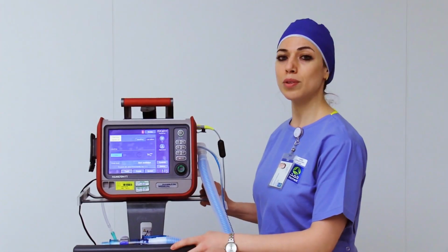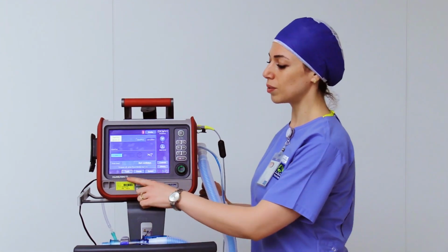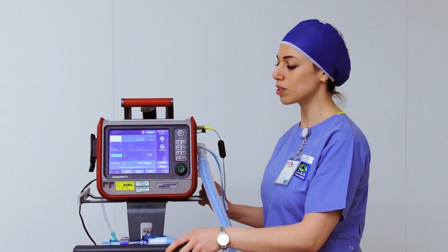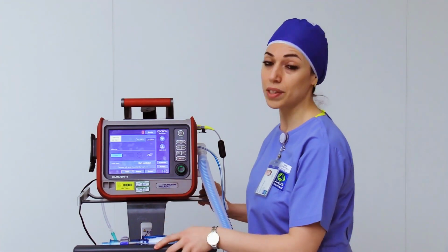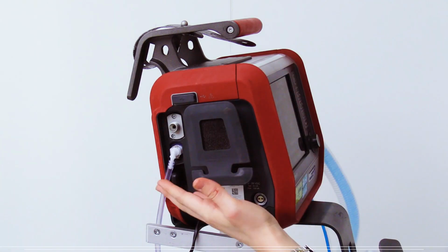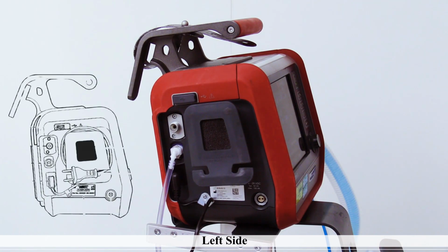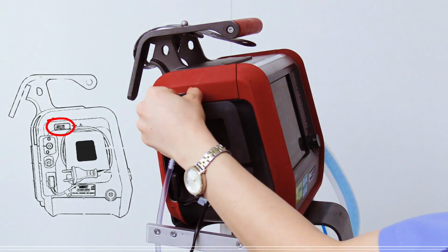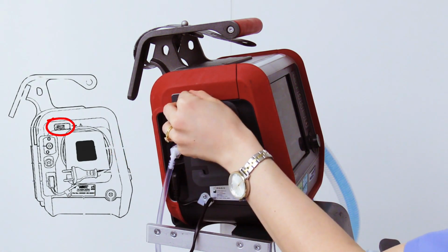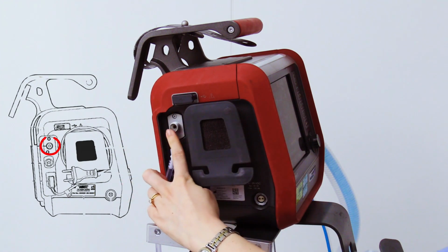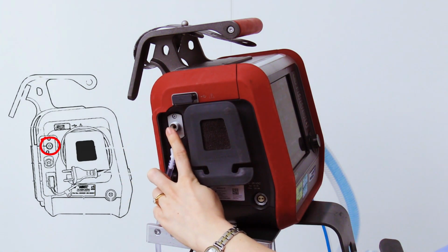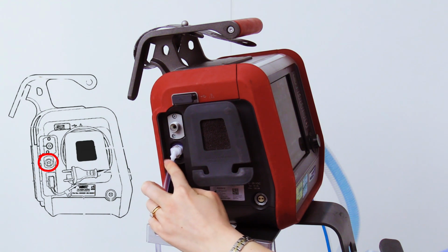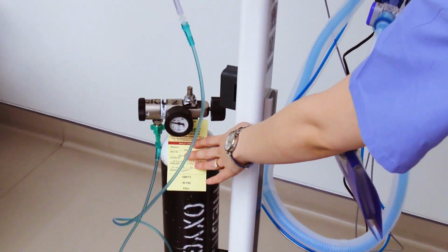Today, I'm going to give you a brief introduction to the Hamilton T1 ventilator, including some information related to the setup and operational steps. First, let's take a look at the left side of the ventilator. This is the USB port for downloading screenshots and uploading software. Here is the high-pressure oxygen inlet that can be connected directly to a gas supply. Below that is the low-pressure oxygen inlet that provides oxygen up to 15 liters per minute from an oxygen cylinder.